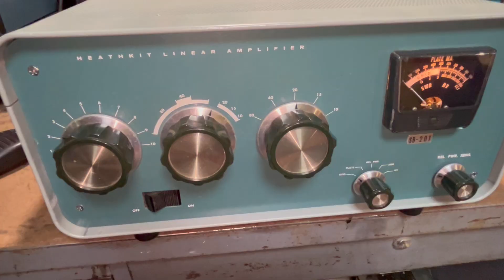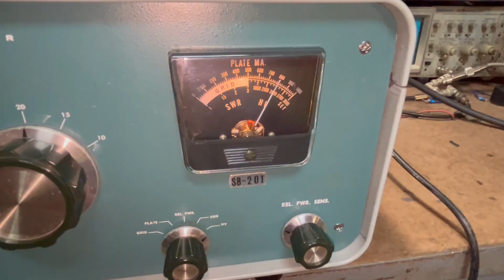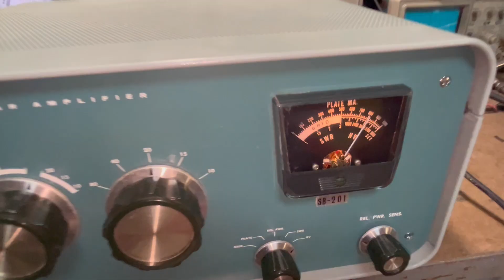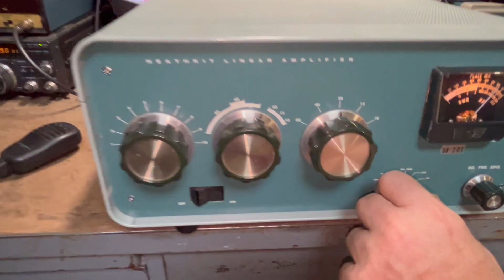So we did that, and the meter did not read correctly for high voltage. Now you can see the high voltage is about 2300 volts or so, maybe a bit over. Before, the high voltage didn't read right on the meter — I think it read 200 volts or something, which I knew was incorrect. The meter resistors were bad and had to be changed. Now we've got it pretty much straightened out.